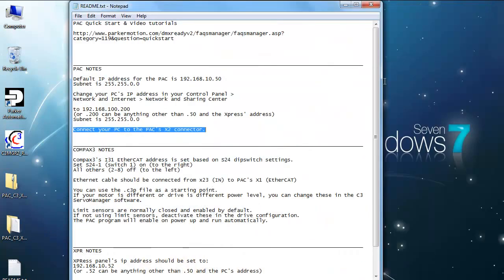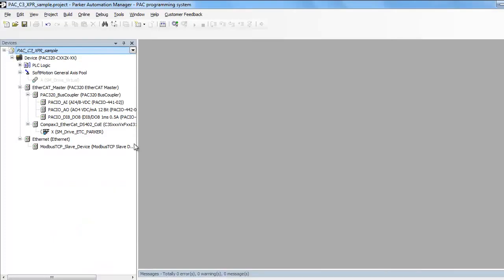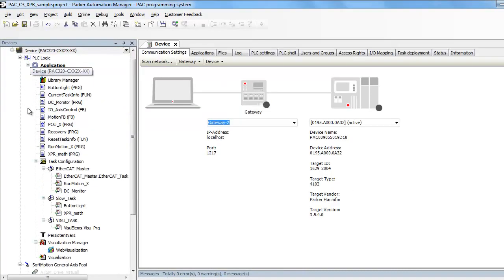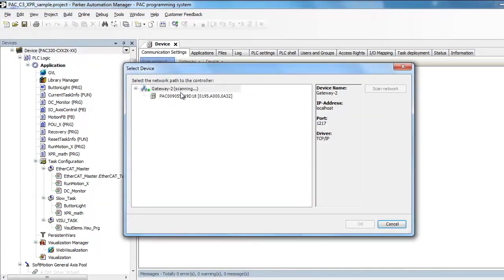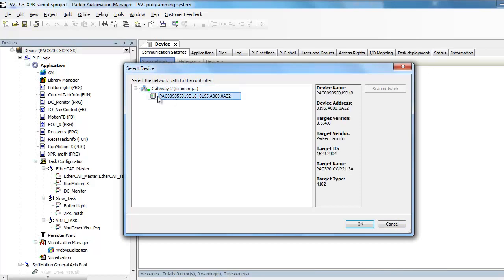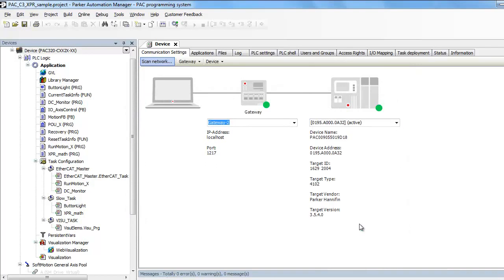Let's go ahead and open up the Parker Automation Manager software. If you double click on the device, click on Scan Network, and then you can see your PAC controller. Go ahead and press OK. The green light indicates that you are communicating to the PAC controller. It does not mean you're actually online with the PLC, but it is communicating.